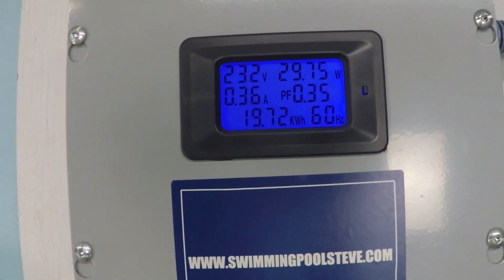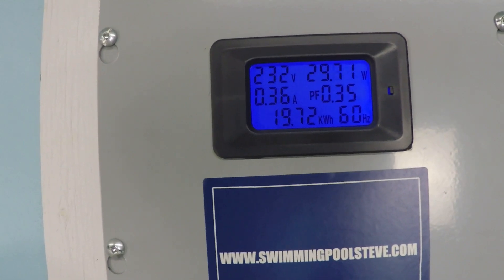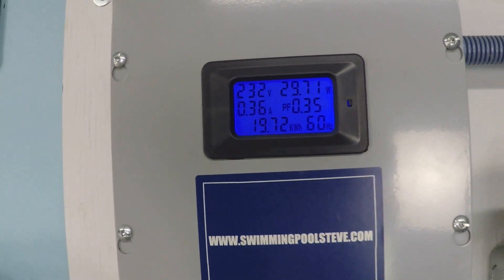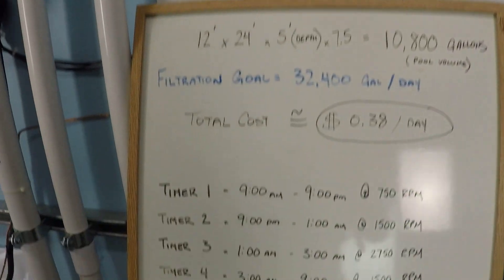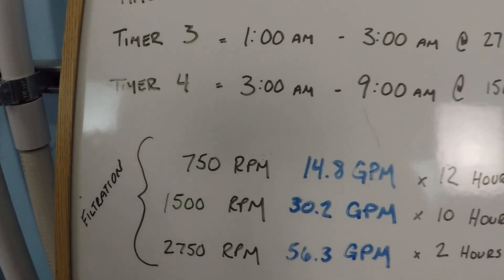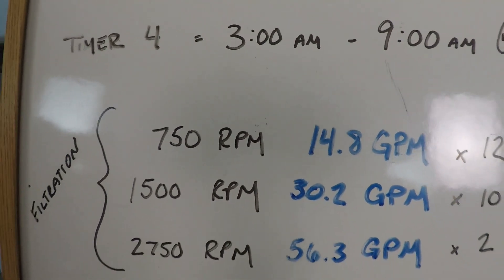Right around 30 watts. Half of a 60 watt light bulb. That's bananas. That's so little power, it's crazy. But as you can see, we're still getting 15 gallons per minute. About 14.8 gallons per minute.